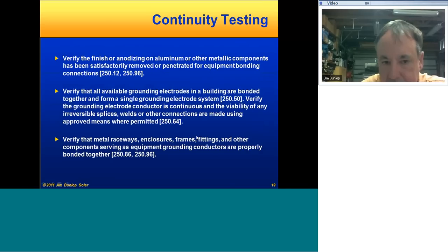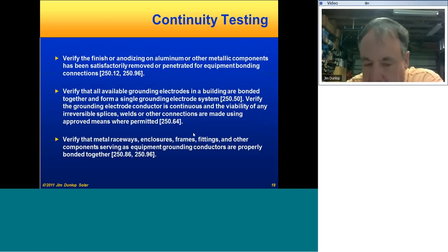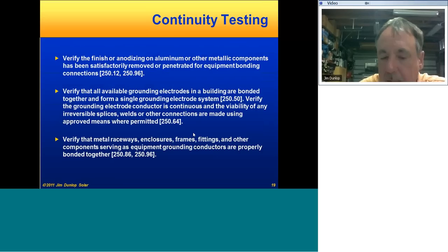Continuity testing, again, I've just listed some things here. I'm not going to get into too much detail with the specific code requirements, but continuity testing is used for a lot of things: to verify proper bonding connections, verify bonding of the grounding electrodes, and proper connections to those grounding electrodes, verifying that all equipment, metal raceways, and equipment enclosures are properly and continuously connected to the equipment grounding system.